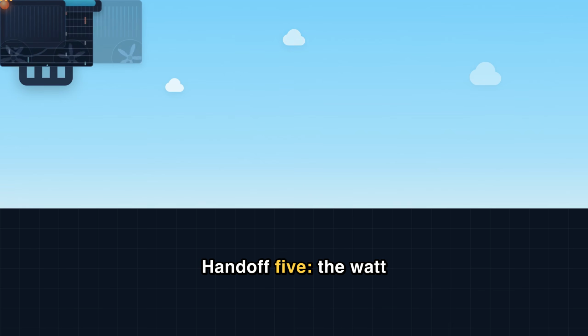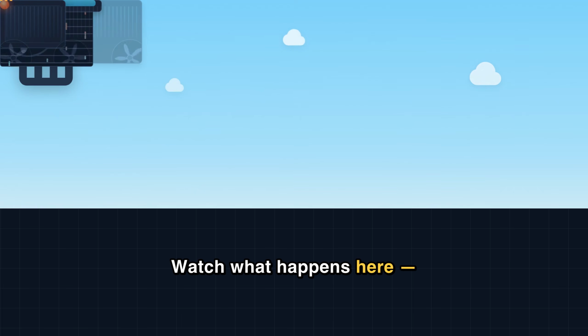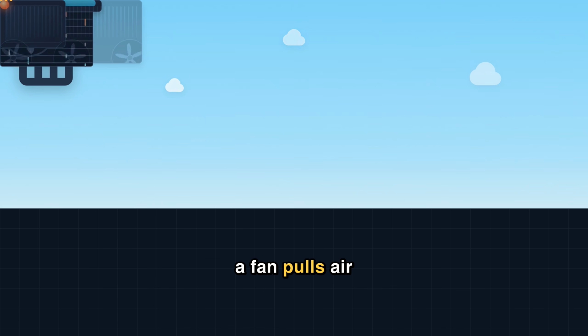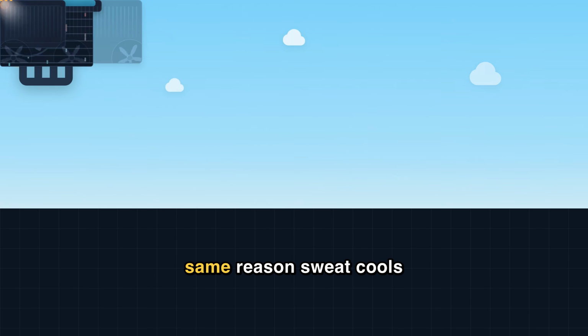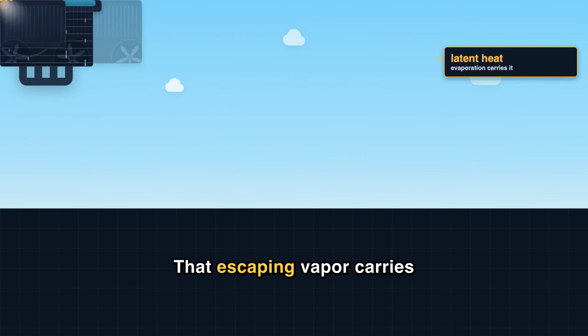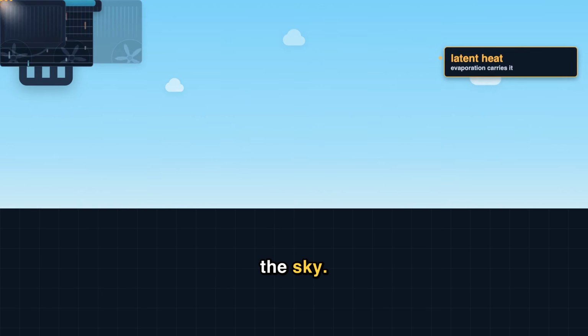Handoff 5. The watt finally leaves the building. The facility water arrives at the roof, at a cooling tower. Watch what happens here, it's clever. The warm water trickles down over slats while a fan pulls air through it, and a little of that water evaporates. Turning water into vapor soaks up a huge amount of heat, the same reason sweat cools your skin. That escaping vapor carries the watt up into the sky. The water that's left behind is now cooler.